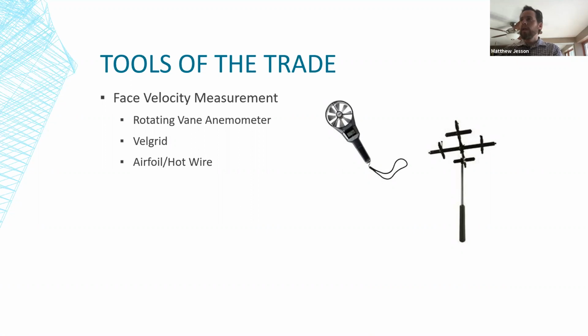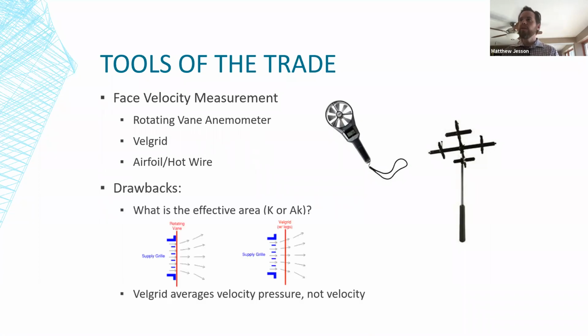The VelGrid to the right there is a plastic grid with basically pairs of holes to measure pressure across the face of it, and that is sort of a proprietary name there, VelGrid, but there isn't really another alternative. You can also use airfoils and hot wires to read face velocity measurement, but the rotating vane and the VelGrid are the most common.